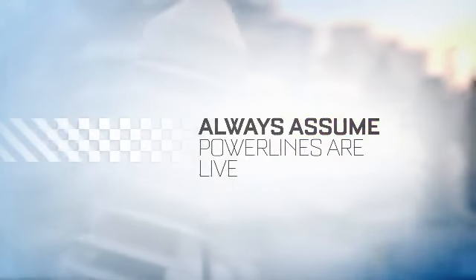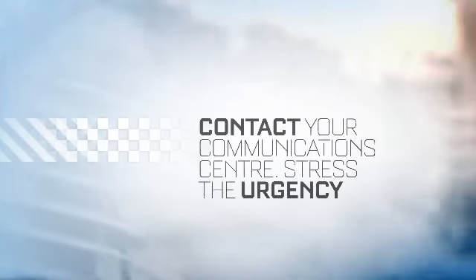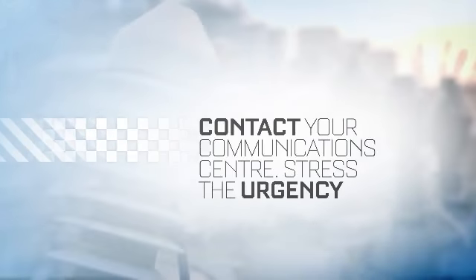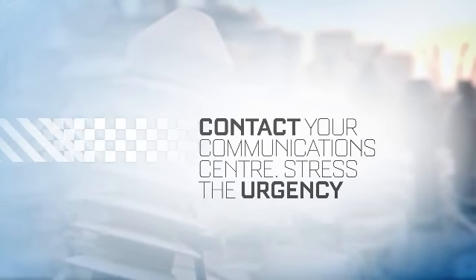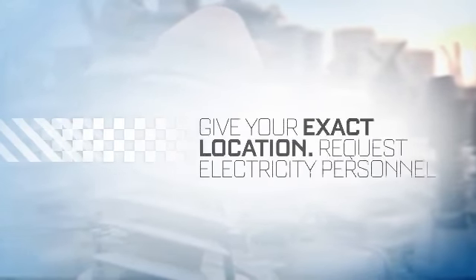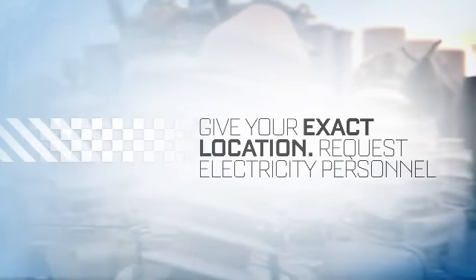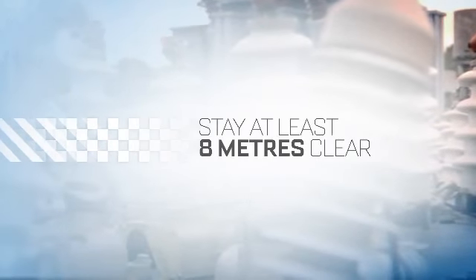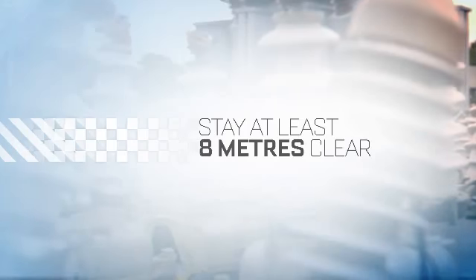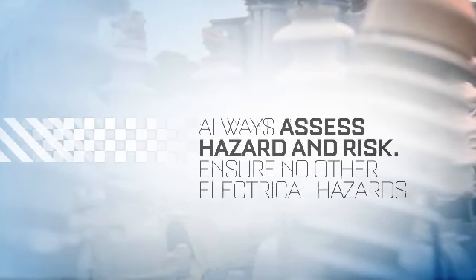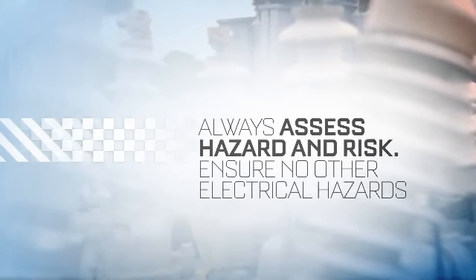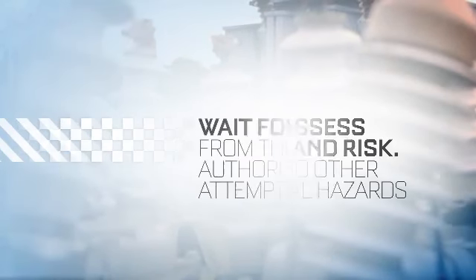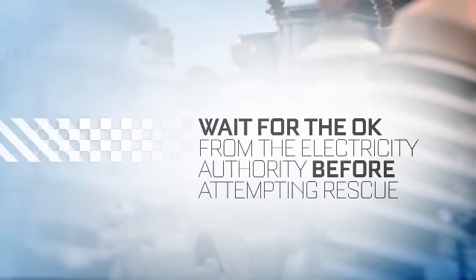Always assume power lines are live. Contact your communications centre in electrical emergencies and stress the urgency of the situation. Give your exact location and request electricity personnel to attend. Keep the area clear and stay at least 8 metres away from fallen power lines or anything in contact with them. Undertake a hazard and risk assessment to ensure that no other electrical hazards are present. Wait for the OK from the electricity authority before attempting rescue.